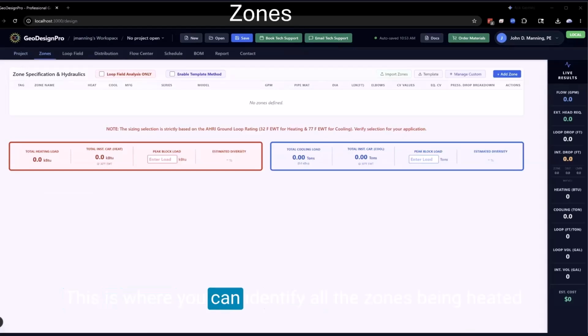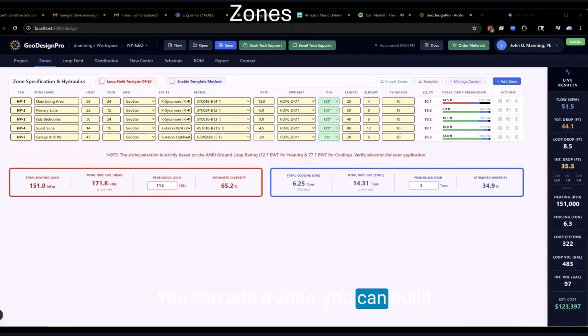Zones. This is where you can identify all the zones being heated or cooled. And the user interface is fairly easy to use. You can add a zone. You can build up the number of heat pumps. You can override the default tag values. You can name each zone. You put your heating and cooling loads in kilobTUs per hour. We don't need to put all 5 digits or more in there. Specify the manufacturer, the series.